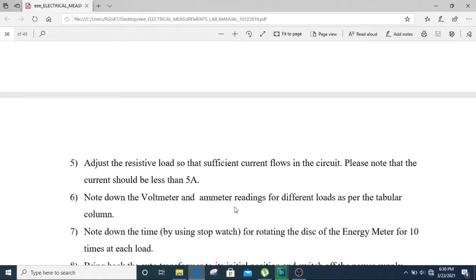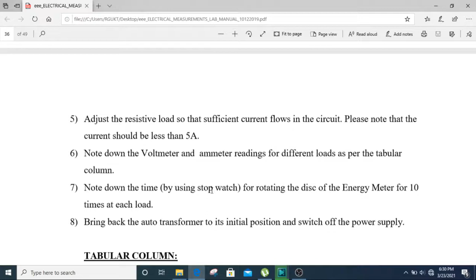You have to note down the time taken by the energy meter to complete 10 revolutions using the stopwatch. Voltmeter reading into ammeter reading into the time taken by the energy meter to complete 10 revolutions will be the true energy. The energy measured by the energy meter is 10 revolutions by 3200 revolutions per kilowatt hour, which gives the energy measured by the energy meter, that is the measured value.